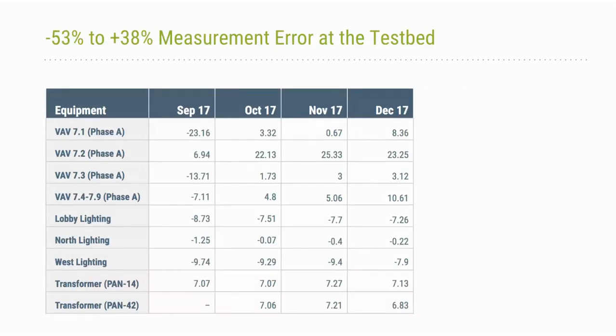And here is a table for the devices that we were comparing. The first 4 are going to be VAV boxes, so they are heating and air conditioning systems. Then we have 3 lighting systems. And on the bottom 2 is the transformer, and I'll explain a little bit more on that. But if we focus, there's a lot of variability in the error, and this was energy error for each month. There's a lot of variability on the VAV, and that's because there's a lot of cycling, and the different months have different average temperatures. So you would see that they cycle a lot more, a lot less, and that actually affects the error that we get.